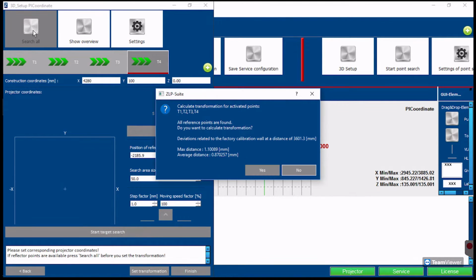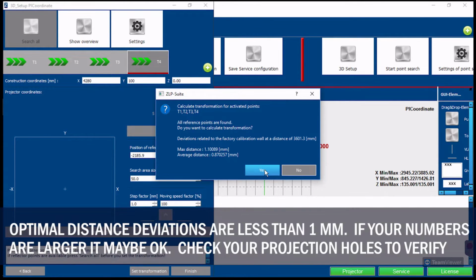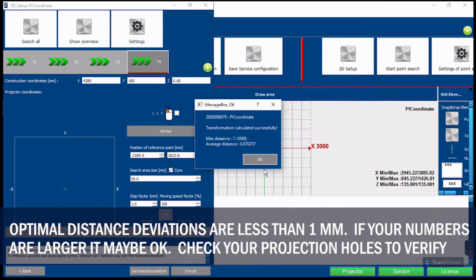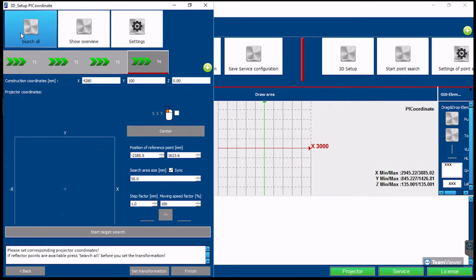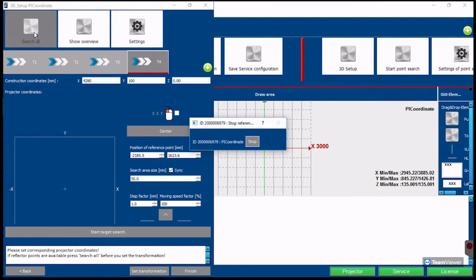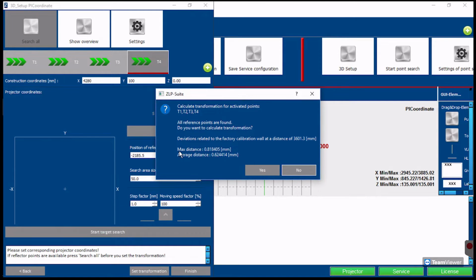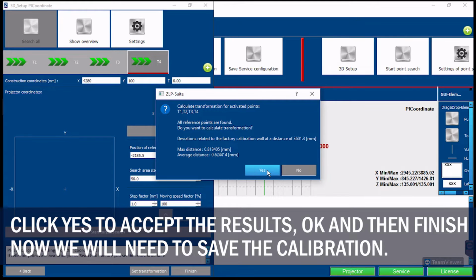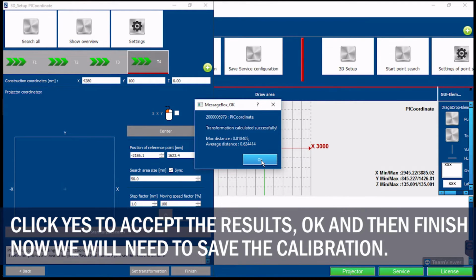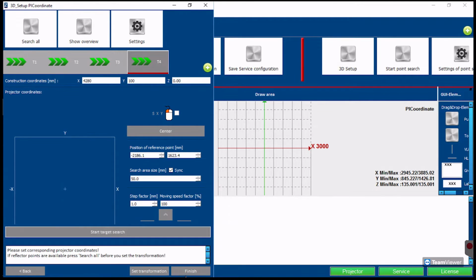When the scanning is complete, you'll get a pop-up to acknowledge that it found all 4 targets. Watch your max and average distance. Optimally, we want them less than 1 millimeter. If it's more than 1 millimeter, double check that the targets are flat against the table, oriented towards the laser, and scan again. Once your results are acceptable, go ahead and click Yes, and then OK to save your transformation. And then you go ahead and click on Finish to exit out of this.